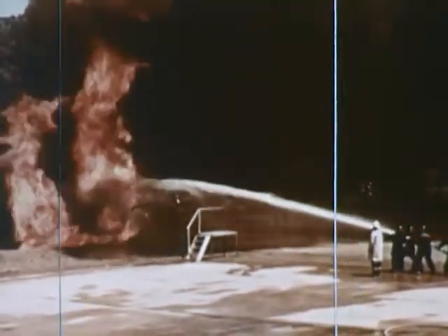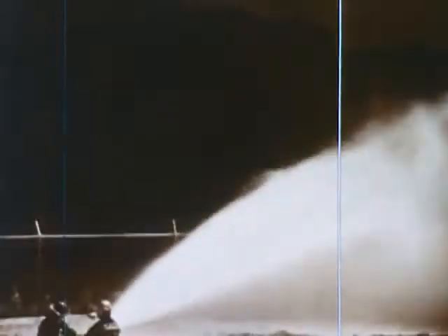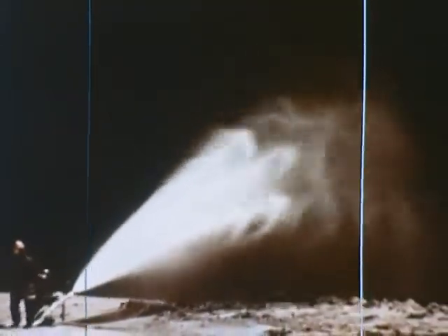The sound from the vent on the horizontal tank indicates that the pressure is gradually building up in this tank. Experience proves that the weak roof-to-shell seam on most vertical tanks, when overpressured, only partly tears the roof loose. Nevertheless, you can expect failure of the roof whenever there is an internal vapor air explosion. Many fires in tanks originate with a vapor air explosion, and occasionally tanks containing fuel oil or similar high flash point liquids will have an internal explosion during an exposure fire when the liquid is heated.